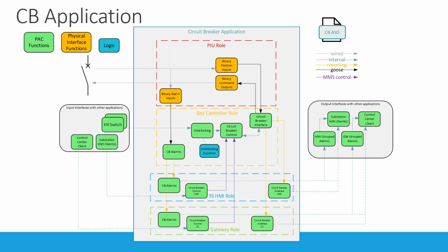From top to bottom, there are inputs that wire the position of the circuit breaker, outputs that wire the trips and the open and closing commands, and some alarms related to the circuit breaker entering through a wired signal. Inside the bay controller we have interfacing, controlling, and interlocking, with an interlocking equation attached. This is an example of attaching the specification of logical behavior to a function. The alarms are sent to the HMI and the gateway, and controlling can be done from those two places as well.